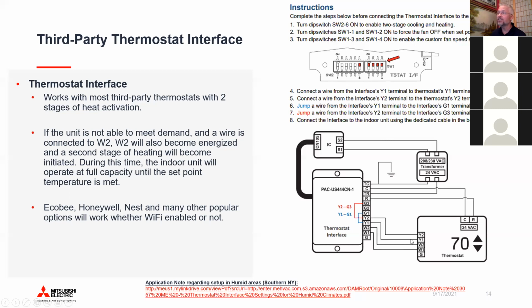You can see these kinds of wiring diagrams and pick the one that's most appropriate for the application. When you're using this third-party thermostat interface to do integrated controls, you're basically just making a dual fuel thermostat, right? You're saying heat pump first, conventional heating system second. Within the controls of your thermostat, whether it's a Nest or an Ecobee or Honeywell, is where you would adjust and set the droop or the outside temperature or whatever else. My strong recommendation is just to set up a droop temperature of a couple of degrees and a delay of 10 or 15 minutes, something like that.